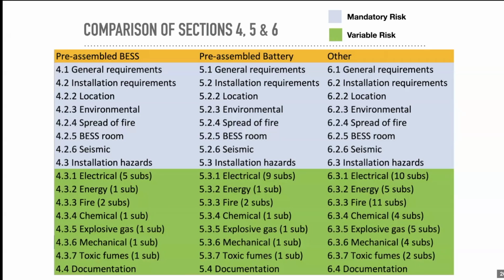The green section in general is known as variable risks, where these risks are based on assessment of that particular installation. So there might be mechanical, electrical, energy, fire, explosive gases, etc. There's a whole bunch of variable risks. For instance, if you have a battery system that emits no explosive gases, you can ignore that section or that subclause. When you get to Section 5, the middle column, you'll notice that there's quite a few more electrical subclauses. That's because of the installation of cabling between a battery system and PCE, being inverters or charge controllers. And then you get to Section 6, which I say is the toughest to comply with because there is a lot of subclauses in all those variable risks.